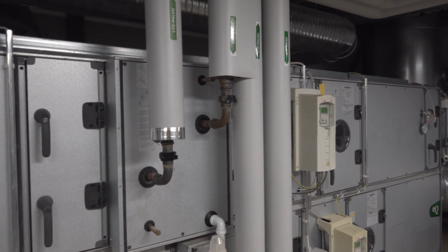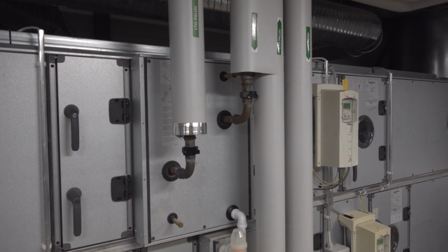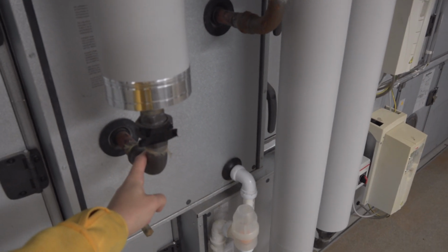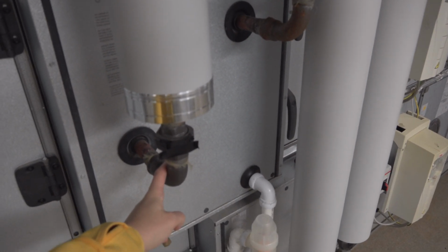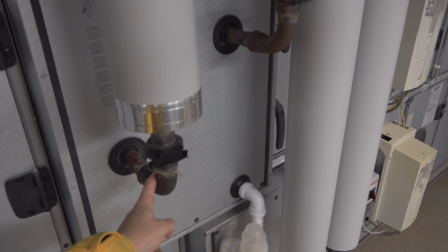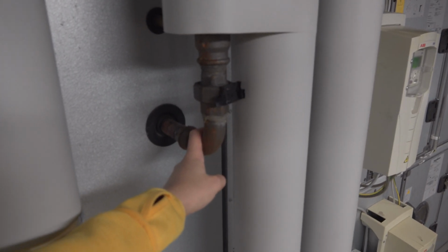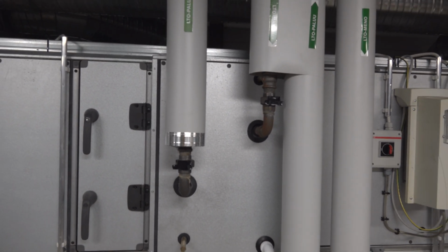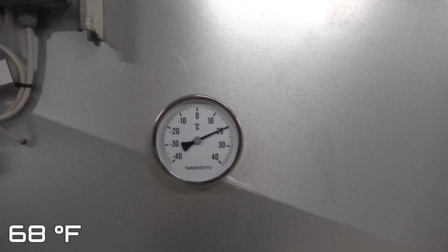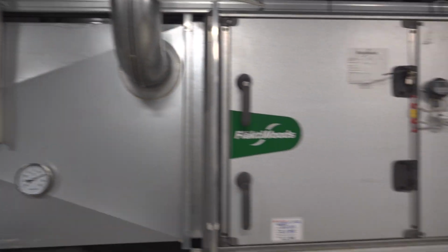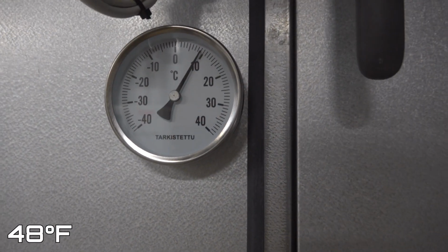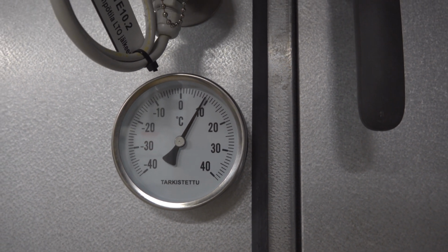The heat exchanger has two tubes, one inlet and one outlet. Cold water ethylene mixture goes in from here and picks up the heat from the air and comes out here as a bit warmer, meaning that it picks up thermal energy from the airflow going through the output side. If we check the temperature in the input side air box coming from the apartment, it's about 20 degrees. It goes through the heat exchanger and the motor, and here you can see the output air going to the roof, which is about 9 degrees. So it has gone 11 degrees down on its way there.